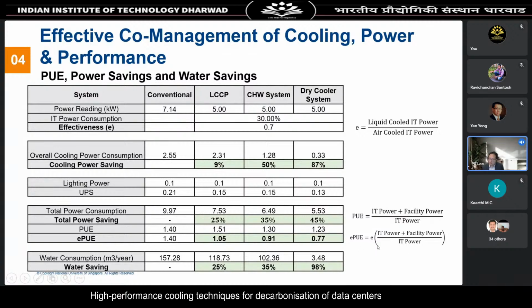That's why we introduced a new definition, the effectiveness PUE. It involves an E factor, defined as liquid-cooled IT power divided by air-cooled IT power. In our case, since liquid cooling slashes IT power by 30%, this E value is 0.7. With this new definition, you can very clearly make the comparison: for example, 1.4 versus the most efficient configuration, which is chillerless, at 0.77. This immediately tells you the total power saving is 45%.